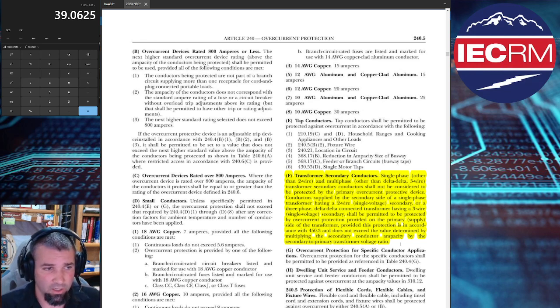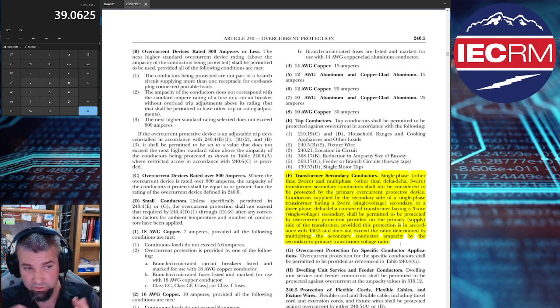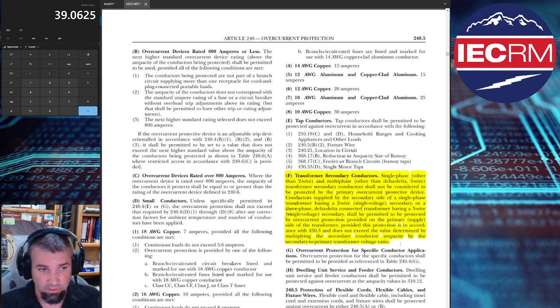It says single phase, other than 2-wire, and multi-phase, other than delta-delta, 3-wire transformer secondary conductors shall not be considered to be protected by the primary overcurrent protective device. Conductors supplied by the secondary side of a single-phase transformer having 2-wire single voltage secondary, or 3-phase delta-delta connected transformer having a 3-wire single voltage secondary shall be permitted to be protected by overcurrent protection provided on the primary supply side of the transformer. Okay, a lot of words. Single phase 2-wire is kind of what we wanted to isolate from that. This last sentence is what's going to be the most pertinent to us, though.